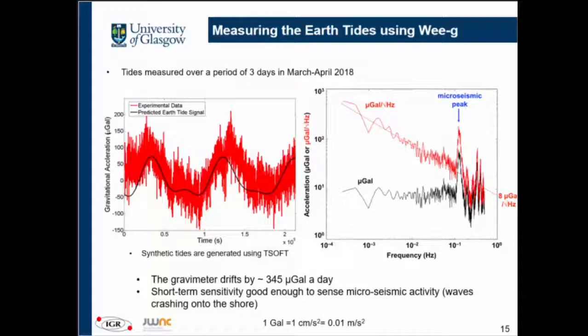Our sensor drifts by about 340 to 345 microgal per day. The CG5 commercial gravimeter I showed earlier gives 500 microgal per day, so we are slightly better than that.